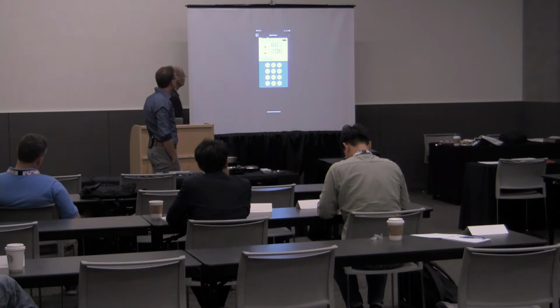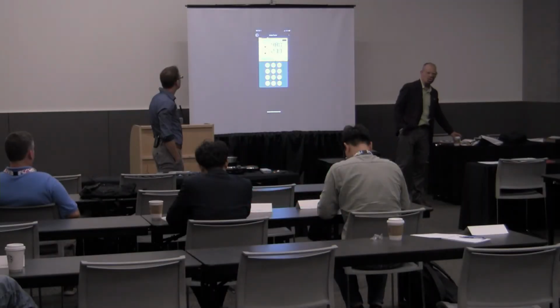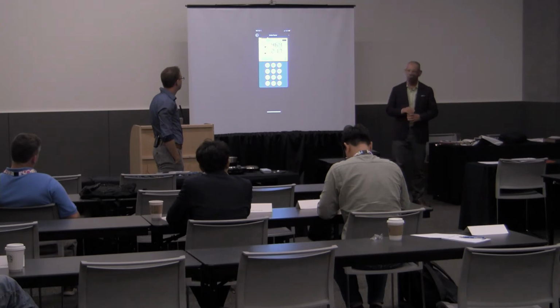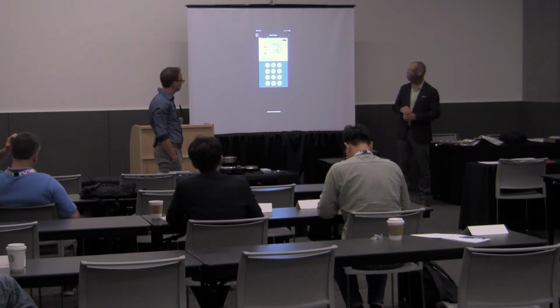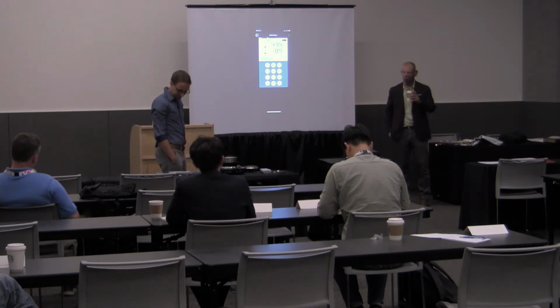If you go back to the interface, we also put in these indicators of the direction that the temperature is actually trending. So they go out. Let me grab this wire probe. Go ahead. Normalize it. You can see now it's warming back up, and when it stops incrementing, it'll flip polarity. But that's just, as a practice, waiting until it's sometimes a judgment call as to when the temperature has actually achieved equilibrium on the probe, and that varies from operator to operator who spends time being careful. So it's just one minor point.